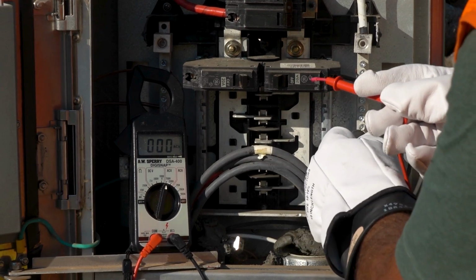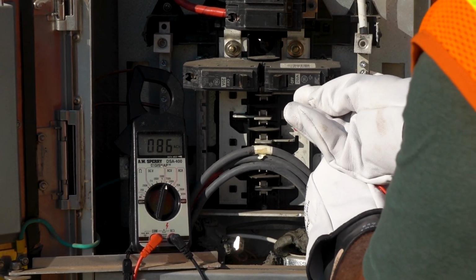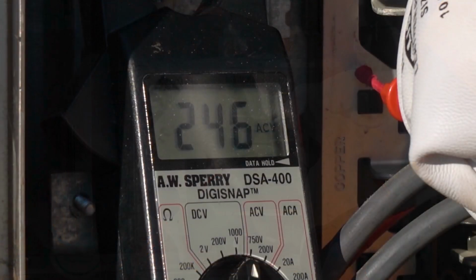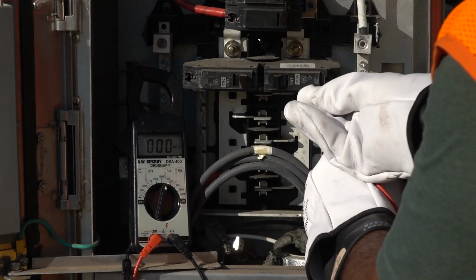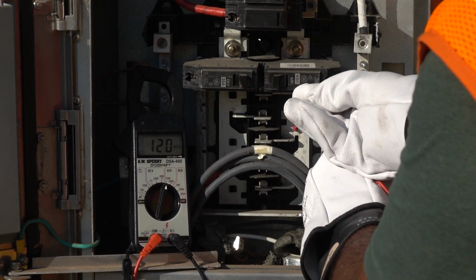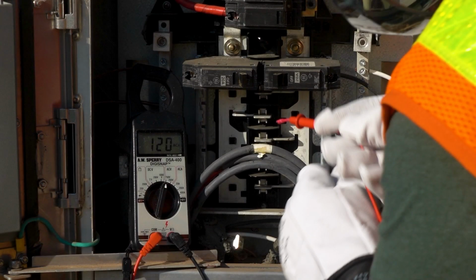On this 120-240 volt service, line-to-line voltage is 240 volts. On the same 120-240 volt service, testing either line 1 or line 2 to neutral, the reading should be 1/2 of 240 volts, which is 120 volts, allowing plus or minus 5%.